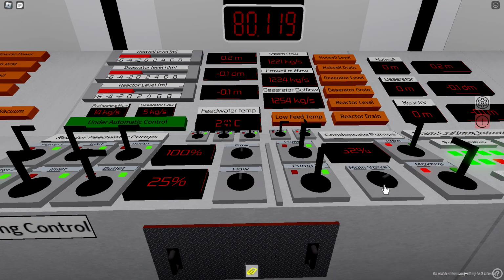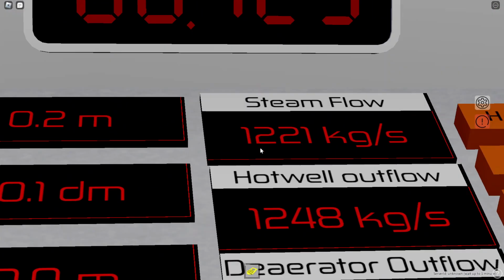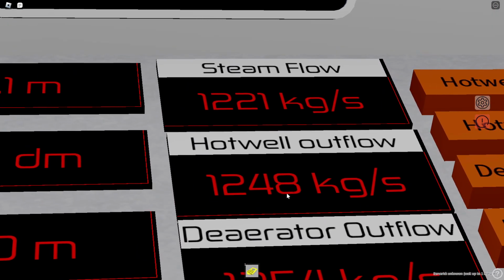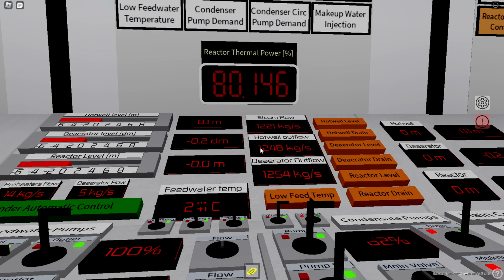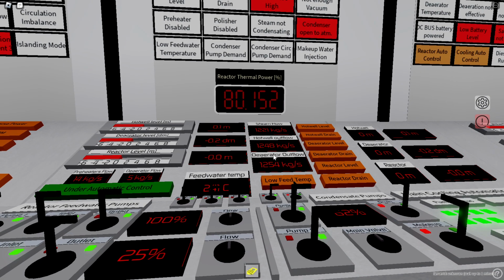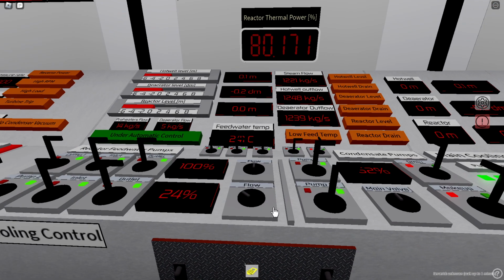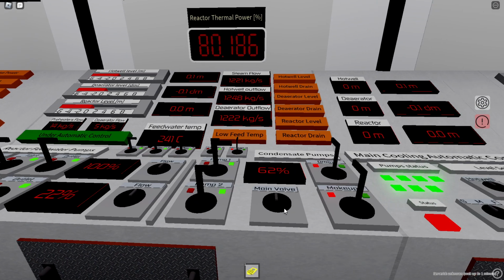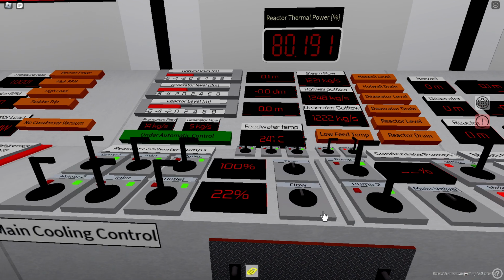So over here, let's say our flows are unbalanced, like this - it isn't very balanced, taking more out of the hot well and then more out of the deaerator. So how to do it: just lower the levels like this, and when you increase it, you have more water going from the deaerator to the reactor, and then the reactor level will increase and the deaerator level will decrease.